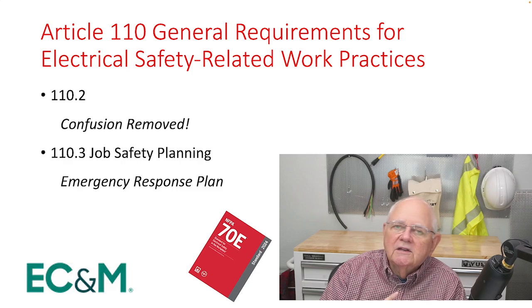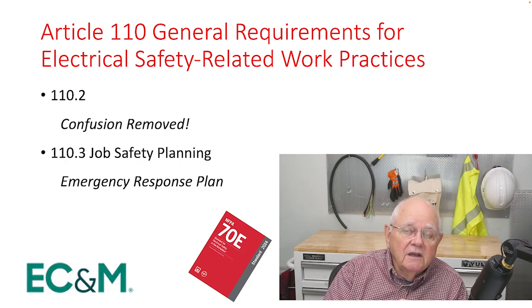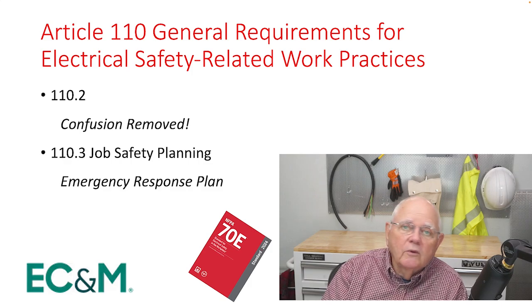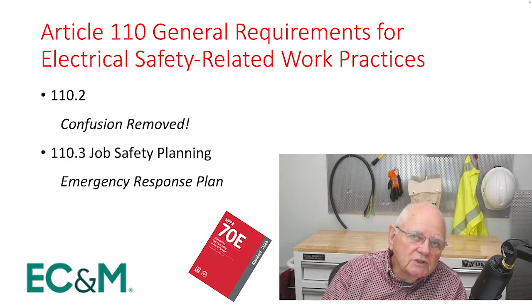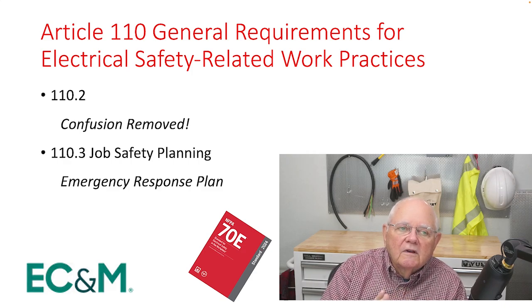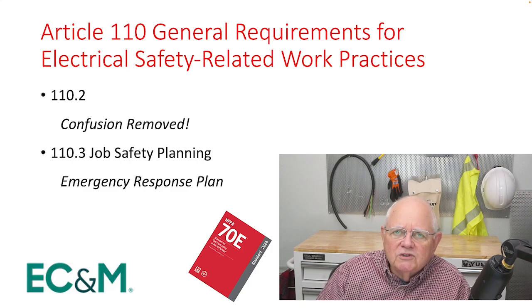110.3 is interesting. Now 110.3 covers job safety planning. It's been in several editions of the NFPA 70E now that we do a written job safety plan before we do our electrical work. There's a new edition that says we must have an emergency response plan as part of that job safety plan. So it goes back to some of your training once again, what all you're going to cover in the training and how you're going to cover that emergency response.